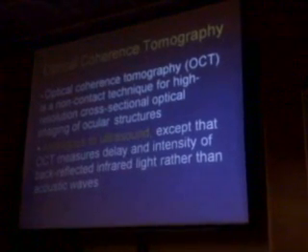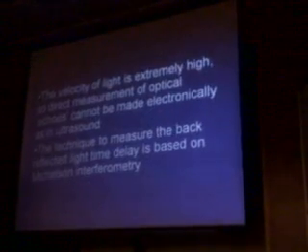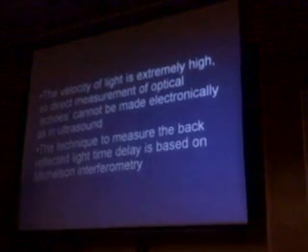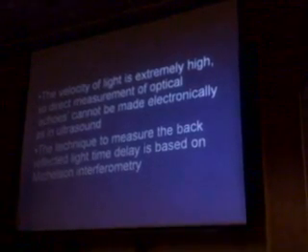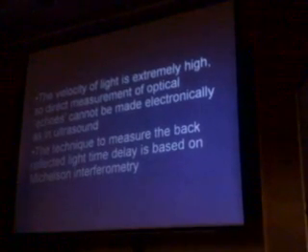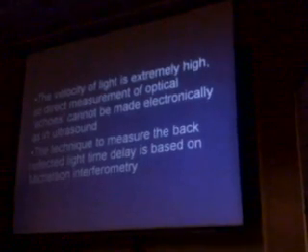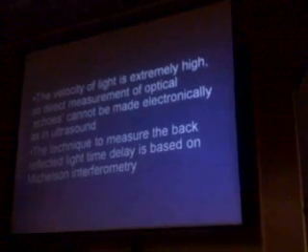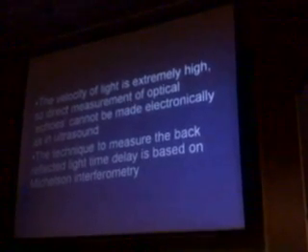Except that the OCT measures the delay and intensity of back-reflected infrared light rather than acoustic waves. The velocity of light is very high, so direct measurement of optical echoes cannot be made electronically like you can in ultrasound. The technique to measure the back-reflected light time delay is based on Michelson interferometry.